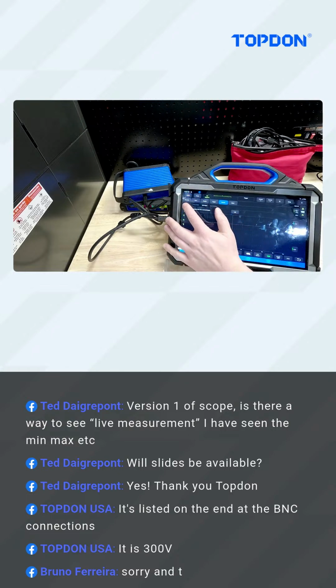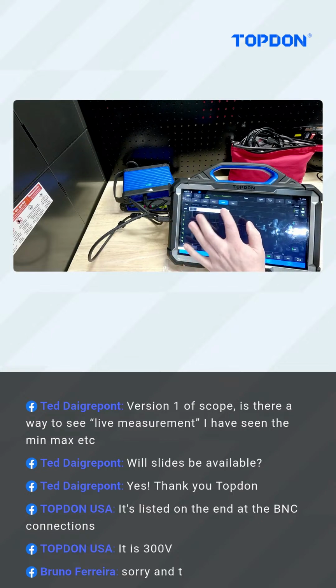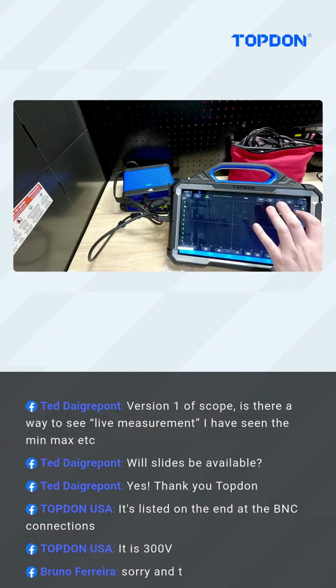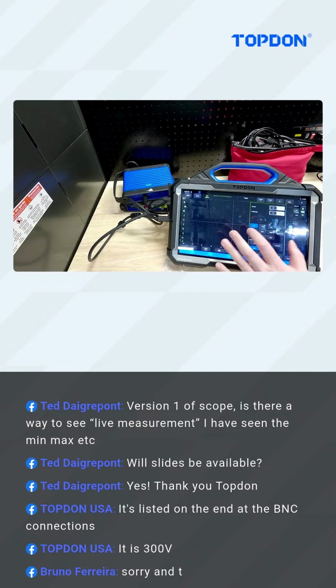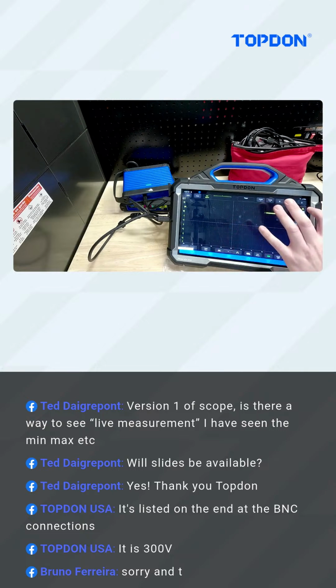So if we're saying, hey, I've got a lot of signal noise, I want to cut that down, maybe we're going to toggle and slow down to a lower sample rate. Again, if you lower your sample rate too low, you may get a distorted waveform. If you raise your sample rate too high, then you may end up with too much signal noise. So just understand that that is something that will affect what you are physically seeing on the screen.